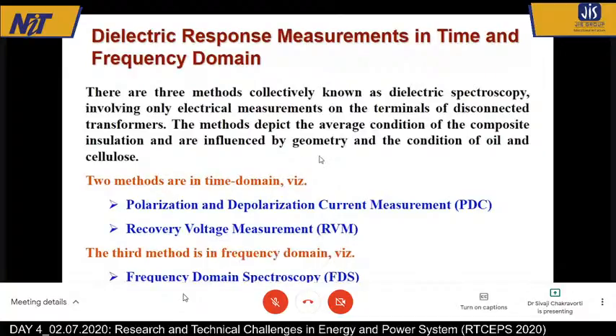Dielectric response is that you apply a voltage and measure the current. It is very simple theoretically. Now, two types of measurements we do. First is called time domain. That means we apply the voltage, and the second is frequency domain measurement. Here we do it in a different way. In the first one, time domain measurement, we apply DC voltage. In the second one, the frequency domain measurement, we apply AC voltage. And we apply AC voltages of different frequencies.